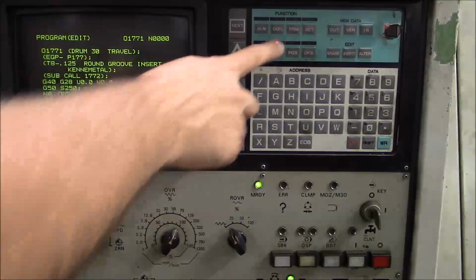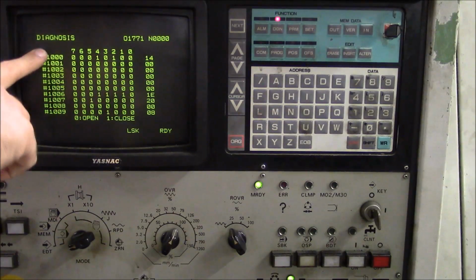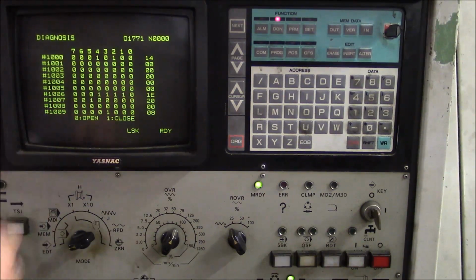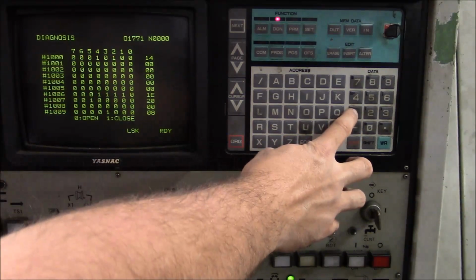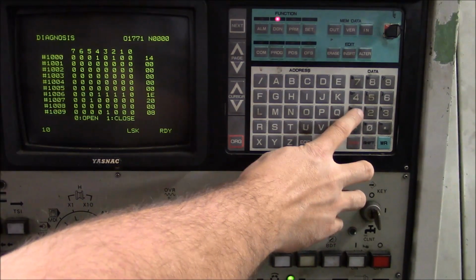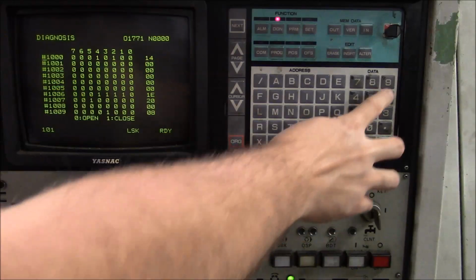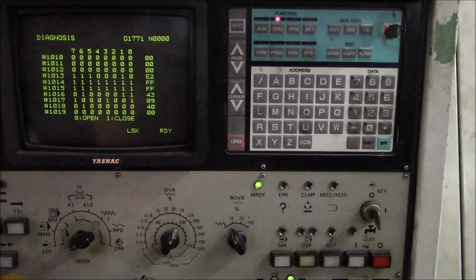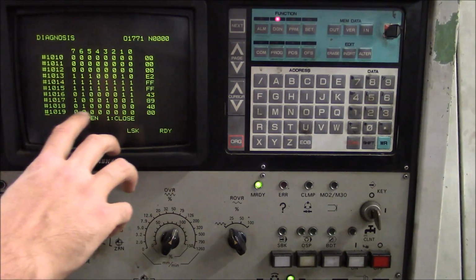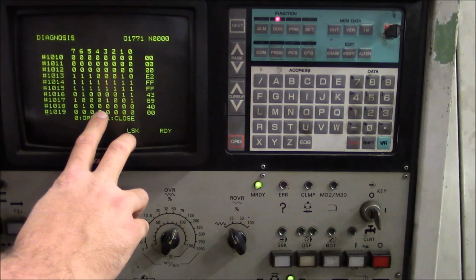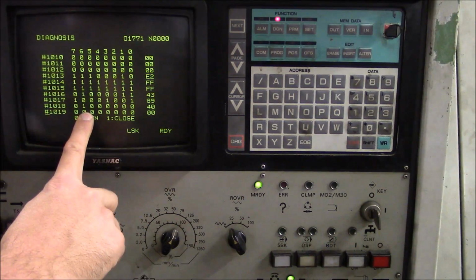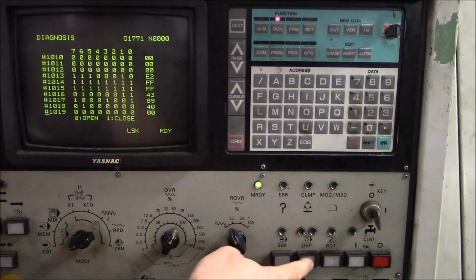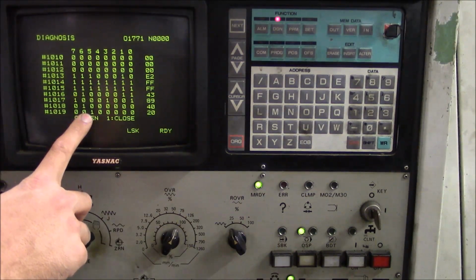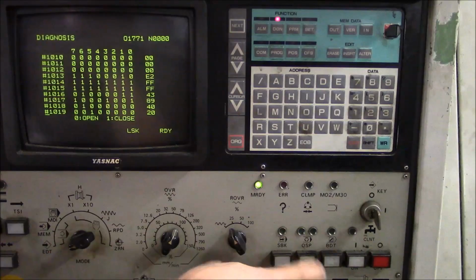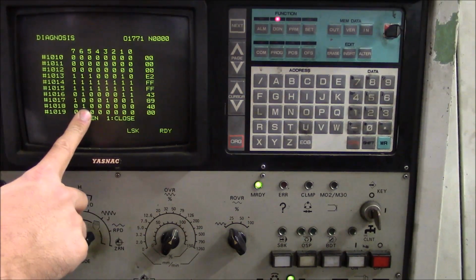The way we do that is just go to the diagnostic page, and you see all these addresses along the side. The one we want is 1019. Hit the cursor down. So here we're on 1019, and it's going to be bit 5, which is this one here. When I hit optional stop, we see bit 5 come on. When I turn optional stop off, bit 5 goes back to a 0.